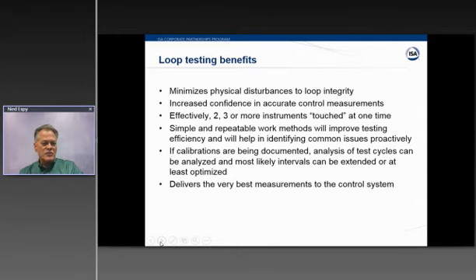And it's also something that if you're doing a lot of temperature loops like this, your personnel is going to have really good standard practices. Everything's going to be repeatable, and you're going to get some efficiency gains. And if you're having to document this, you can start analyzing your test cycles. And if your temperature measurements are staying within control, why test more frequently than necessary? So you can look at your intervals and maybe make some gains there. But the bottom line is you want to deliver quality information to the control engineer. So you want to give the control folks the very best measurement that they can get.